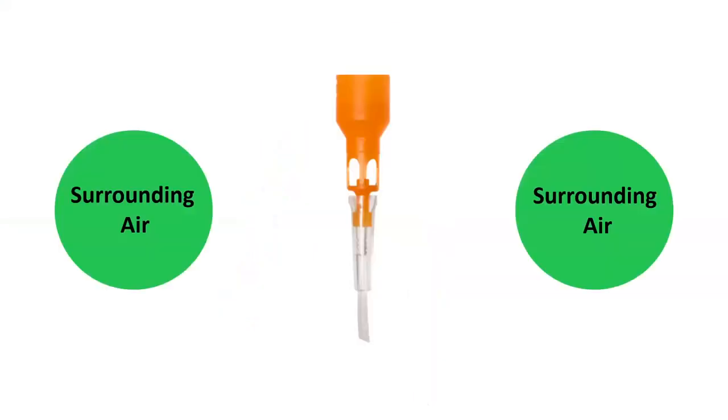So the breakdown of the mask is pretty simple. Oxygen is delivered to this tiny little tube at the bottom. And when the patient breathes in, the mask makes use of the Venturi effect by mixing the higher pressure surrounding air with the low pressure high velocity oxygen traveling through the mask.